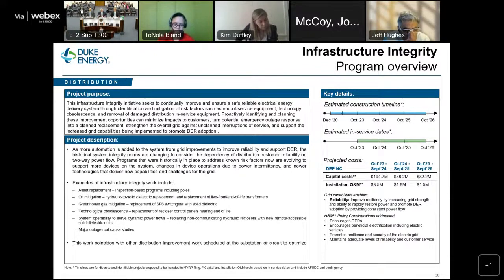Or the example I gave earlier of technological obsolescence for voltage regulators. The current controls cannot control voltage in two different directions. They're simply looking from the substation out to control voltage. The modern controls can determine a stiff source from either direction and properly maintain voltage. And there's a couple of other examples listed also.